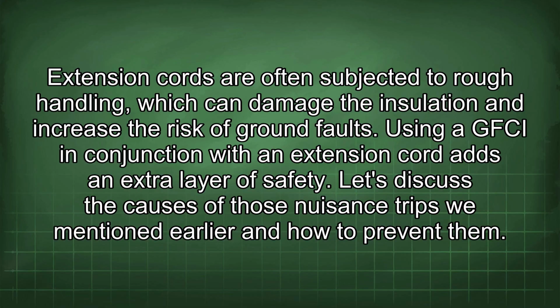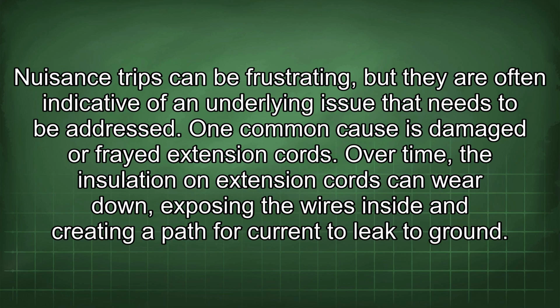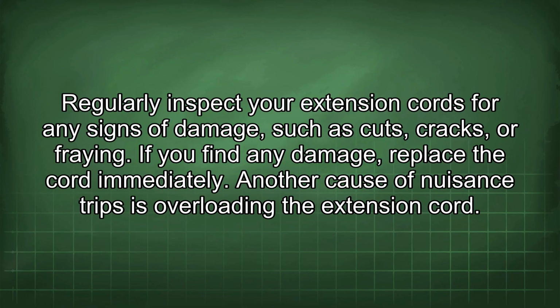Let's discuss the causes of those nuisance trips we mentioned earlier and how to prevent them. Nuisance trips can be frustrating, but they are often indicative of an underlying issue that needs to be addressed. One common cause is damaged or frayed extension cords. Over time, the insulation on extension cords can wear down, exposing the wires inside and creating a path for current to leak to ground. Regularly inspect your extension cords for any signs of damage, such as cuts, cracks, or fraying.